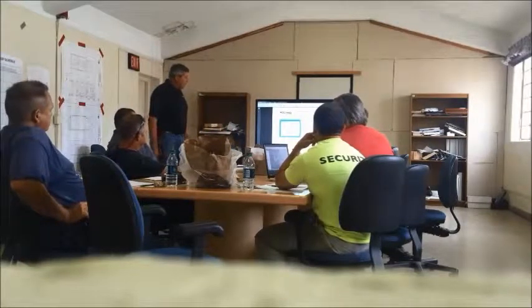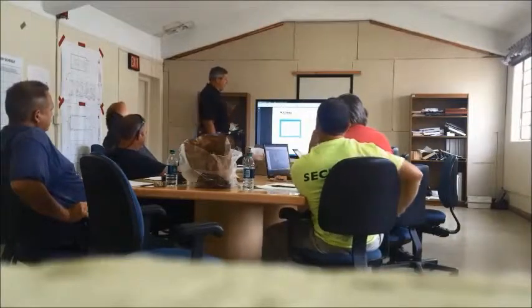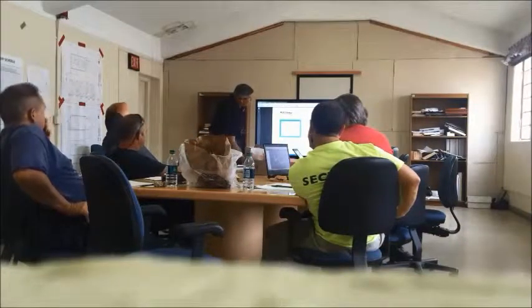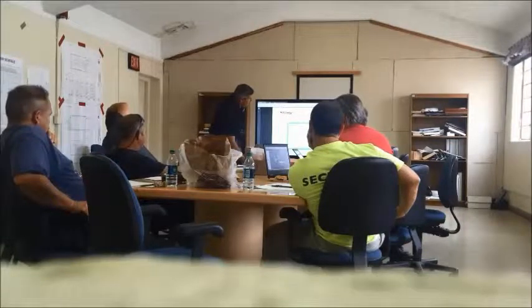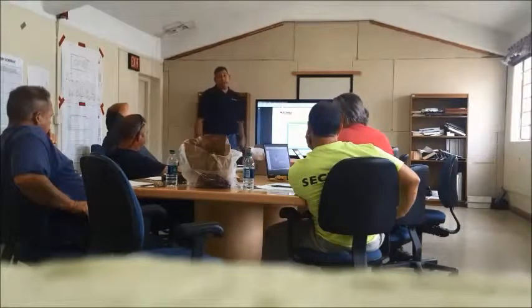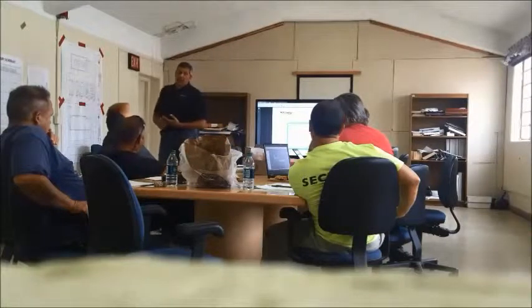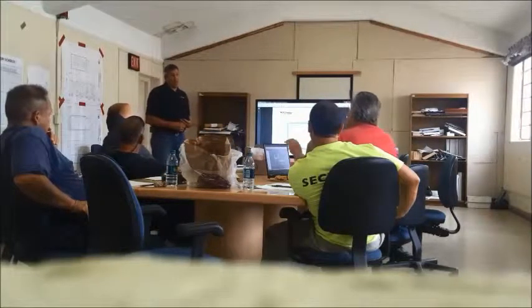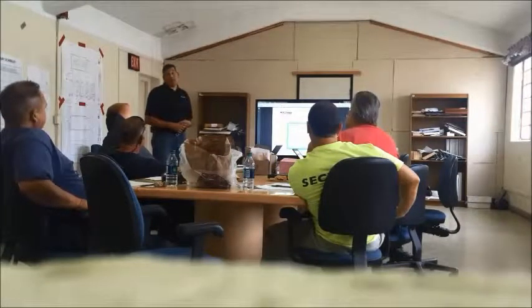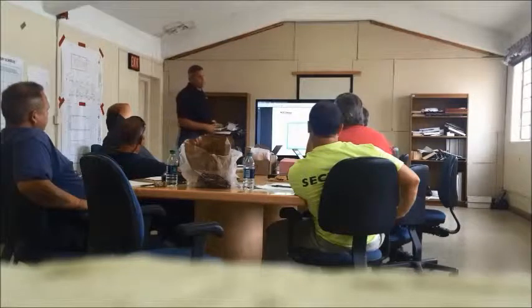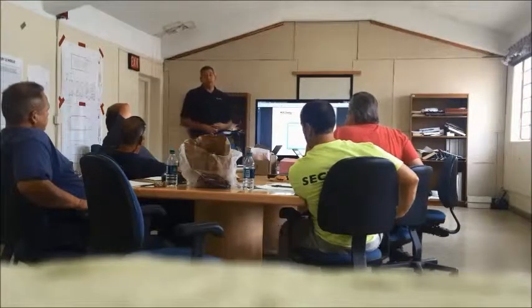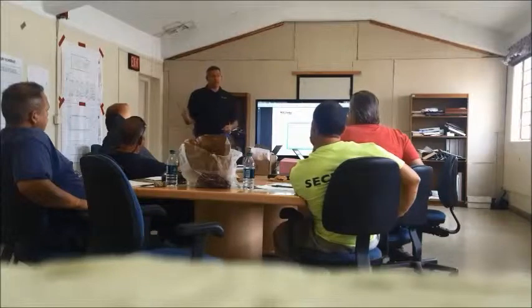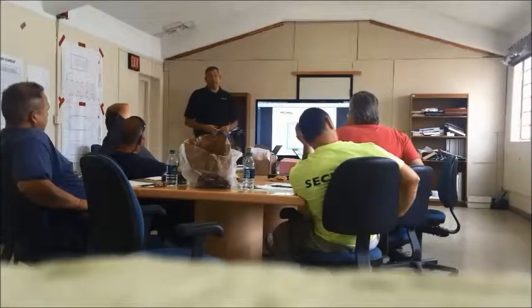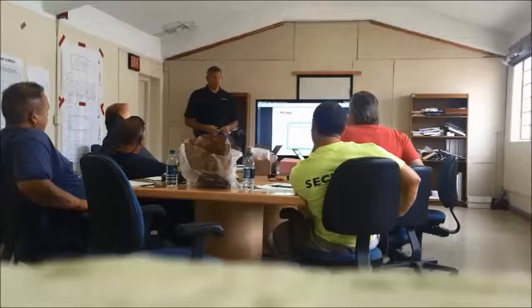Reason why I want to elaborate more on this is that there's a different function on here that's important. And that is not just a standard operation. In this setup, I can't see it here in this display, there's actually a setup for fire life safety mode, which is very, very convenient. Unfortunately, a lot of labs in the past, when you go through a fire life safety event, the exhaust has to keep running and the supplies go off. So inherently you have a set point of 1.5, all the supply or makeup air goes off, and all your rooms become highly negative. So you can't even open the doors.